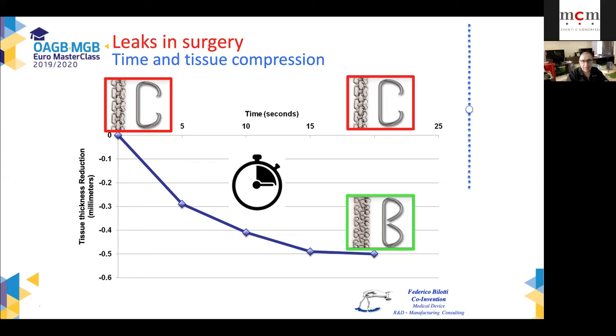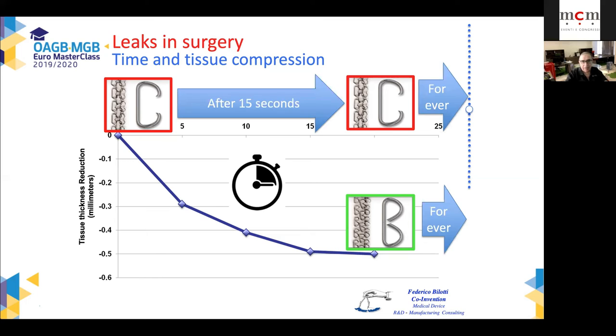So you say, why wait 15 seconds? Why waste my time? What you should then consider is the fact that the patient goes home, and if you don't wait 15 seconds, the patient will go home with open staples, and forever you'll have that staple formation. But the tissue changes, becomes thinner and thinner and drier and drier. So if there is a possibility of leakage, it will be with a tissue that is compressed improperly because you didn't wait 15 seconds. The tissue could bleed 1 day later. As Sakran noticed, there is leakage even 2 or 3 days later.